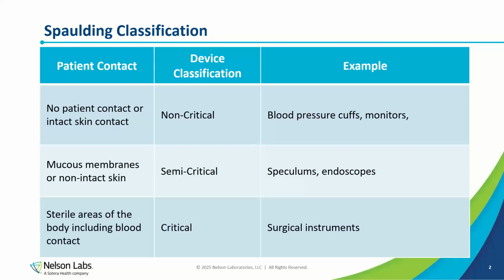And with these devices, semi-critical devices, they need to go through cleaning and then ideally sterilization. However, a lot of semi-critical devices cannot be sterilized, and in those cases, high-level disinfection may be appropriate. And high-level disinfection is the minimum requirement, essentially, for semi-critical devices.